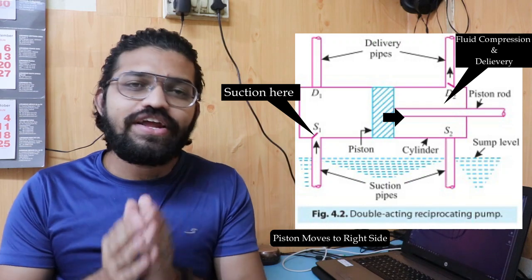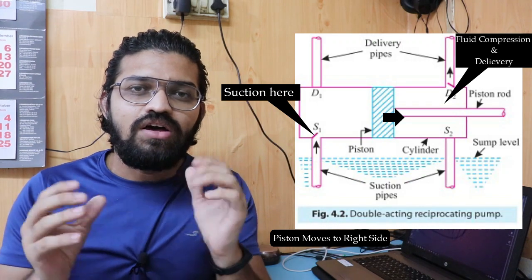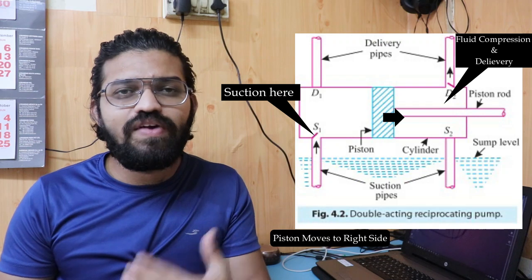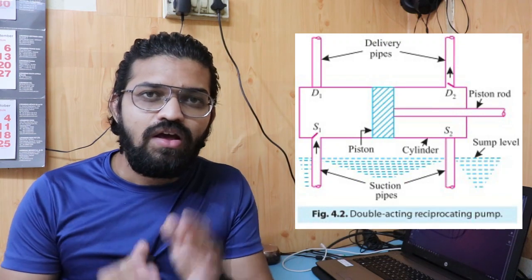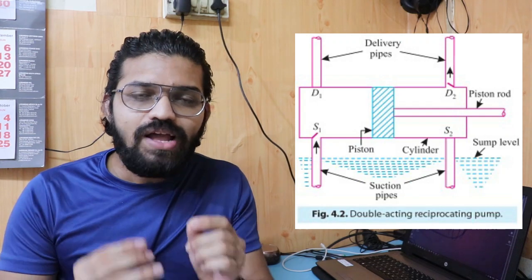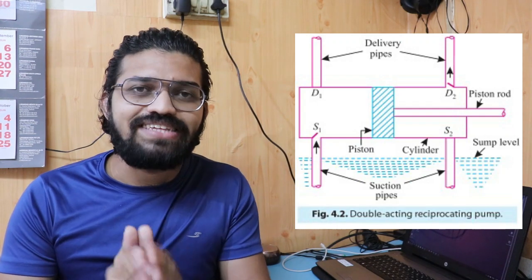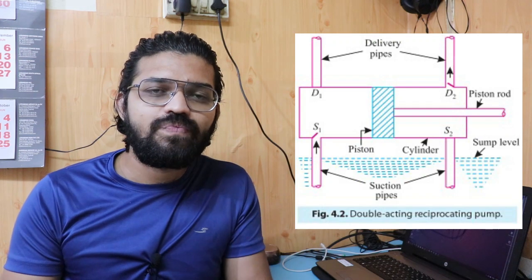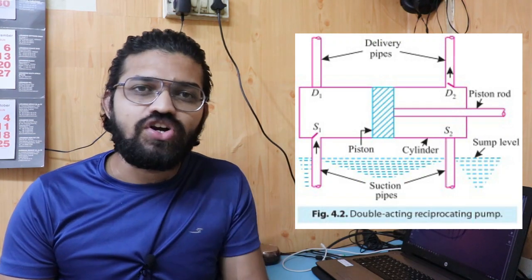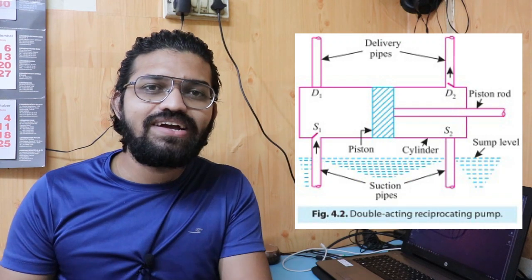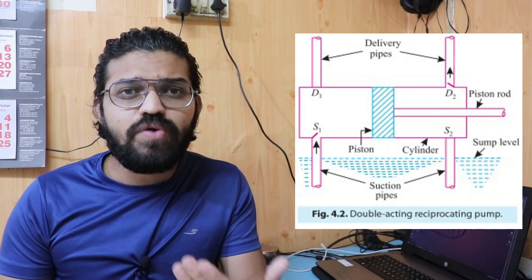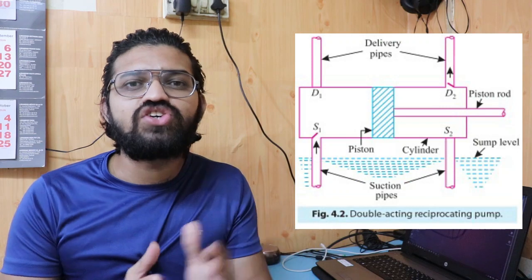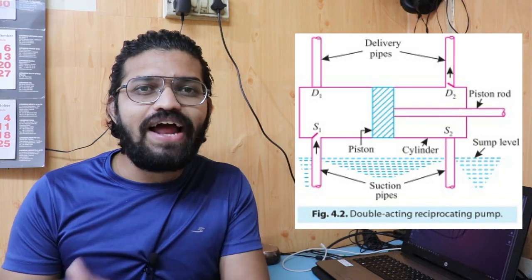This is the overall working of the double acting reciprocating pump. We have reduced the intermittent flow and get a more continuous discharge compared to the single acting pump. However, a limitation of the double acting reciprocating pump is that it cannot produce as high a pressure as the single acting type, which can produce up to 250 bar. The discharge per minute, however, has been increased.